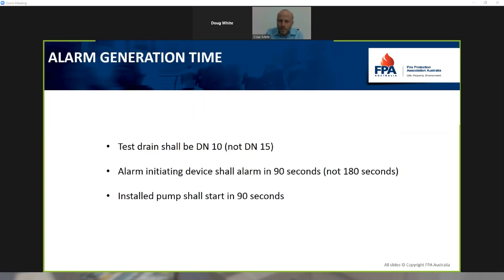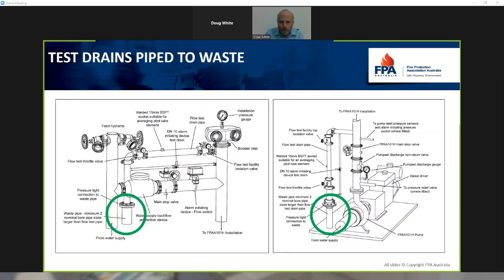Pumps also are required to start within 90 seconds in this spec. Another thing we've included here is to hydraulically connect our drains. We know it's been a big problem to have a drain running inside of a larger pipe, and when you do your flow test, it backs up and causes all sorts of problems. We now want these hydraulically connected so that we can make sure that we're achieving our flow rates and test them routinely without any grief, or less grief.